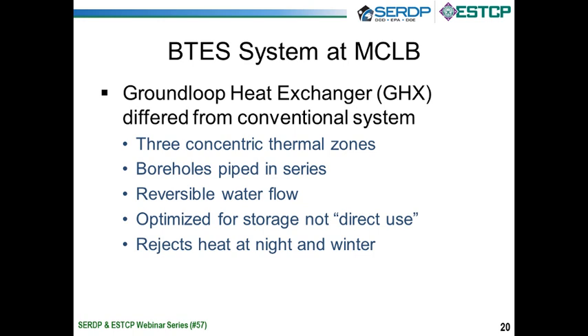The other unique thing about a BTES system is reversible water flow. In traditional geothermal heat pump systems, the water flows one way, kind of in and out. We actually can reverse the flow, a little bit analogous to a heat pump where you reverse the refrigerant flow, so that you have a hot coil outside and a cold coil inside when you're cooling, and a hot coil inside and a cold coil outside. Kind of doing the same thing here, but we can reverse the water flow. You'll see why that's important in a minute.